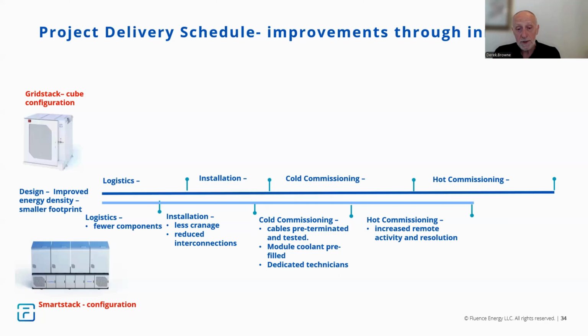Then on to the cold commissioning. On the smart stack configuration, all our interconnecting cables are now pre-terminated and tested. In the case of most of the modules, the coolant is pre-filled, so that saves us a lot of time on site, particularly if you had 500 cubes to fill with coolant. And we now have a team of dedicated technicians whose job is to make sure that we have a fully integrated system ready to energize.